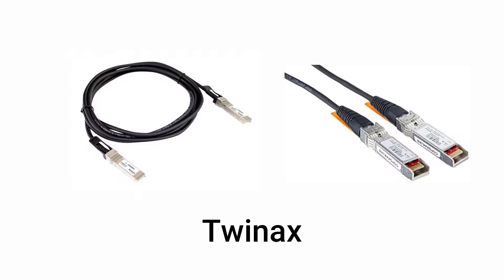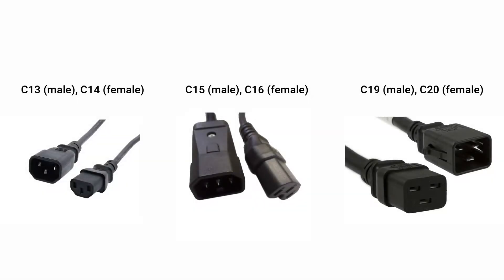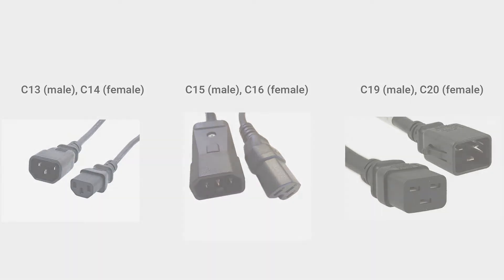Twinax cables are much lower cost, but the negative compared to copper or fiber is that you are limited by length before data cannot be transferred properly. Power cables found on site include C13, which is the male connection, and C14, the matching socket. C15 is a similar shape to C13 with a central notch, and the C15 male plug connects to the C16 socket. C19 is also used and plugs into the C20 socket — C19 and C20 are rectangular in shape.